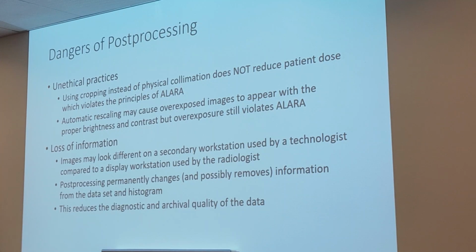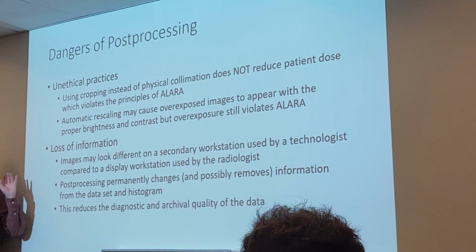Speaking of loss of information, if you window or level your image before sending it over to the radiologist, you are going to cause a loss of information in the raw data. Right? So if they want to window and level themselves, they no longer have as much information to do it with. Okay? So you're saying that we shouldn't mess with the brightness, we should only mess with the contrast? You shouldn't mess with either of them. The image that comes out should be what you send across.